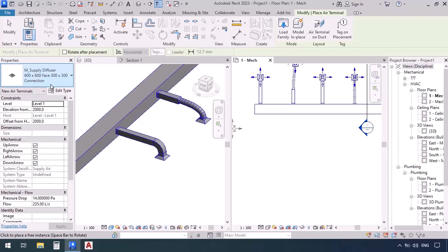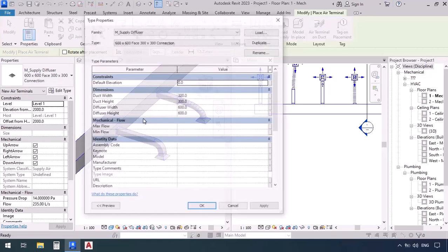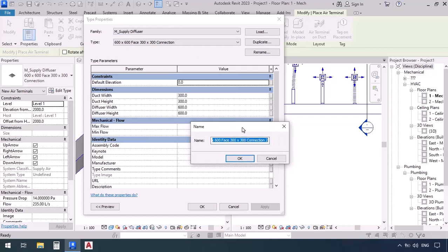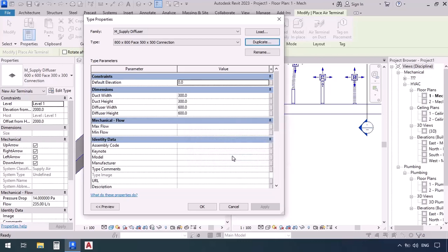What can we do if we have a duct with different sizes than this in the project? We can create a new size. While the terminal is selected, click on 'Edit Type' and a window will pop up with a dimension section. We're not going to change it — we're going to get a duplicate and enter a new name. I'll delete this and enter the name according to the sizes: 800 by 800 face and 500 by 500 connection. Now adjust the sizes from the dimension section — duct width, duct height, diffuser width, and diffuser height.